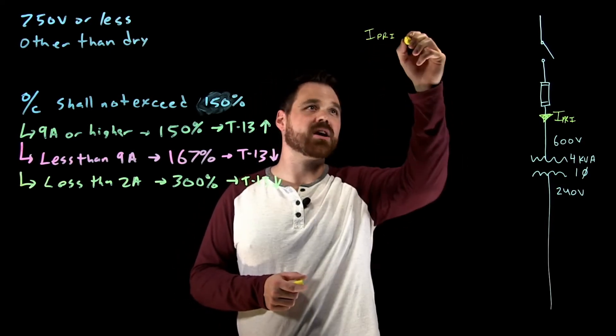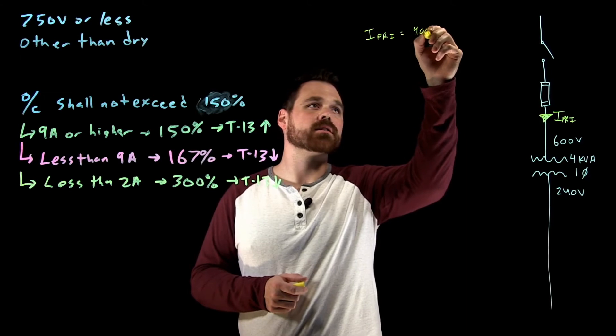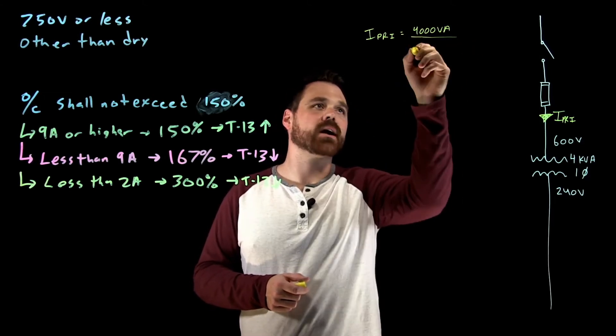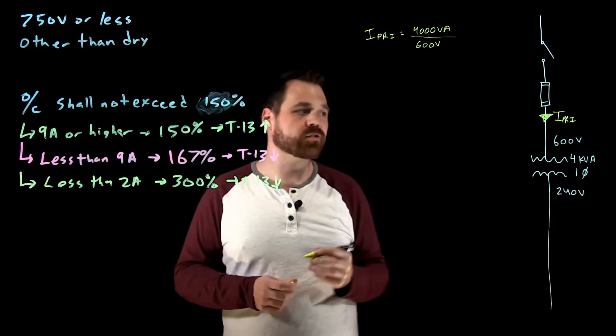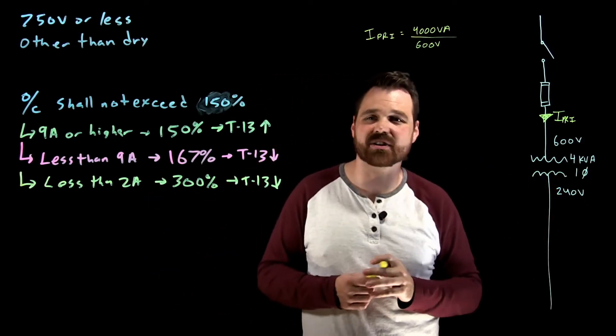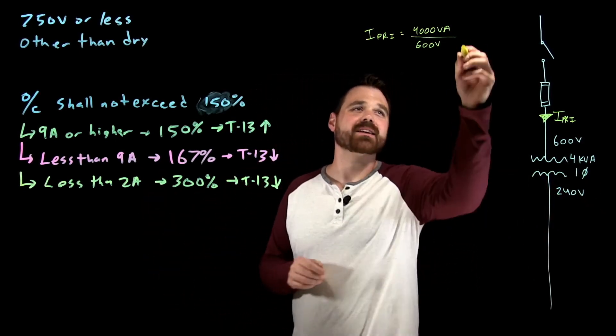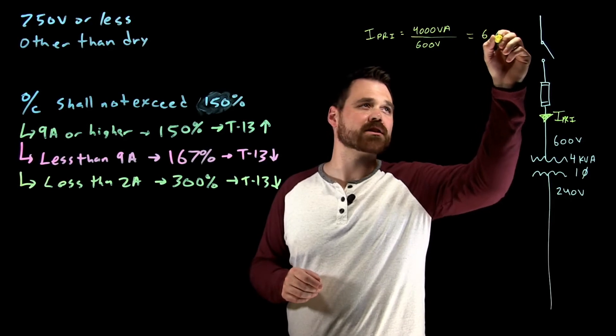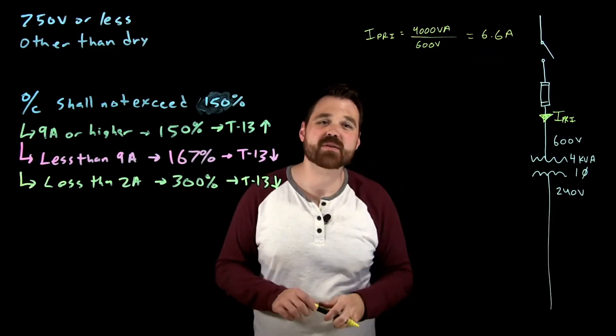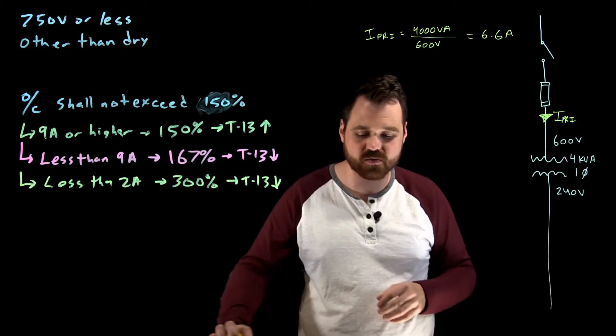I'm going to take my kVA, 4000 VA divided by 600 volts, no root three because we're just talking a single phase transformer. And in this case, I get 6.6 amps. That's my rated primary current of that transformer.